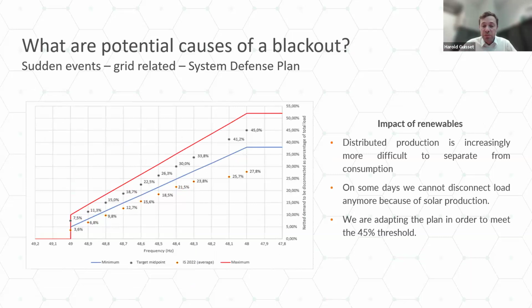So as I said, we have an obligation at a European level to be able to disconnect 45% of the load at every moment in the year. And this measure of last resort, this emergency brake, currently is not working as it should be. And the main reason for that is the penetration of solar. So basically, those frequency relays are installed in substations from Elia and are disconnecting load on the distribution side.